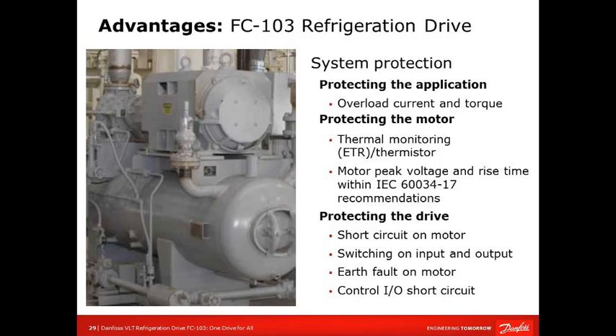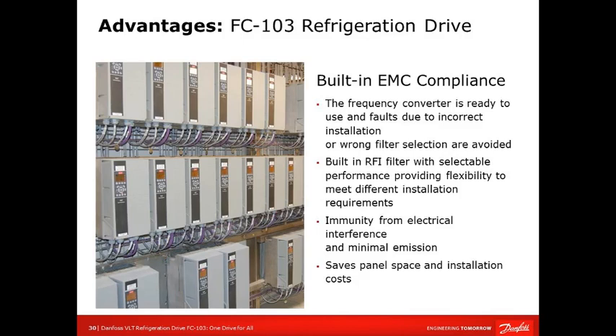Built-in things, these are built into the drive. It's not just specific to the FC-103 for the refrigeration drive, but all Danfoss drives are built to protect the application. So we have built-in protection for overload current and torque, not only protecting the drive, but obviously protecting the motors from short circuit on the motors, switching on the input. A lot of things from our experience are just integrated into the drive, because we want to keep you guys up and running and keep your application and operations running smoothly without downtime. You know, EMC compliance, you'll maybe hear about harmonics and things like that. Danfoss does a lot where we include inside our drive, for example, built-in RFI.